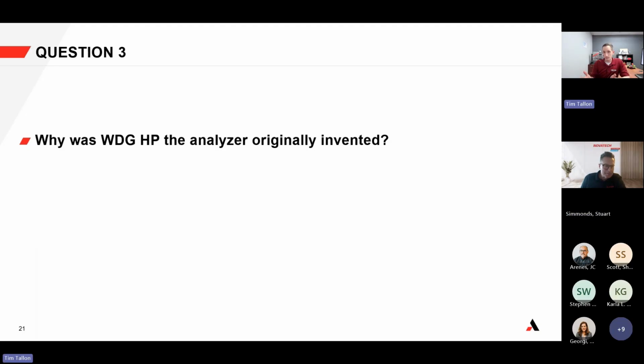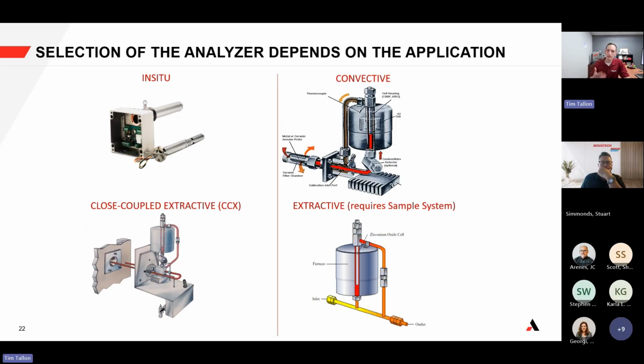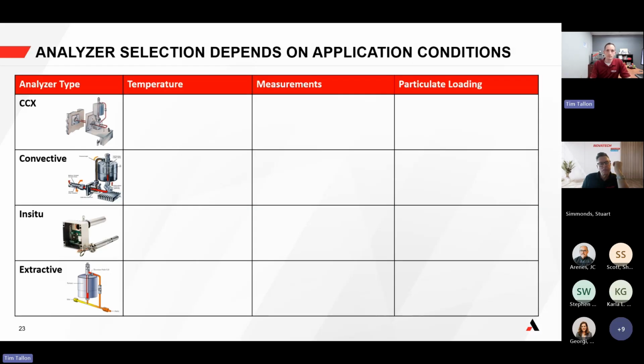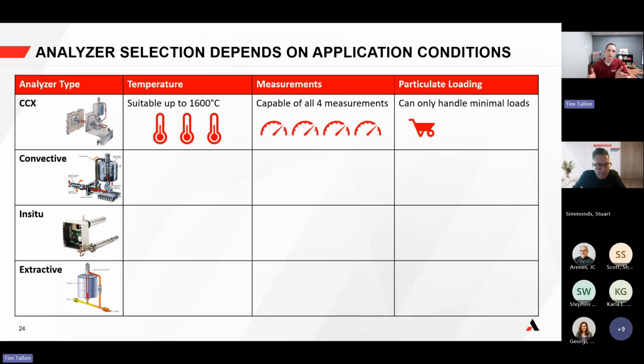Right. It may have been fun building, but it didn't happen by accident, right? It happens for a reason. As we think about applications, AMETEK has over 50 years of experience, especially within Thermox, within combustion control. When you look at it, the selection for analyzers really depends on the application. When you think about high particulate, especially close coupled extractive, or CCX, that works really well for high temperatures. We have different probe options that allow us to operate at 1600 degrees Celsius and lower. We also have the capability of 4 measurements: excess oxygen, combustibles, methane, and flow. Those 4 measurements allow you to detect any amount of plugging.